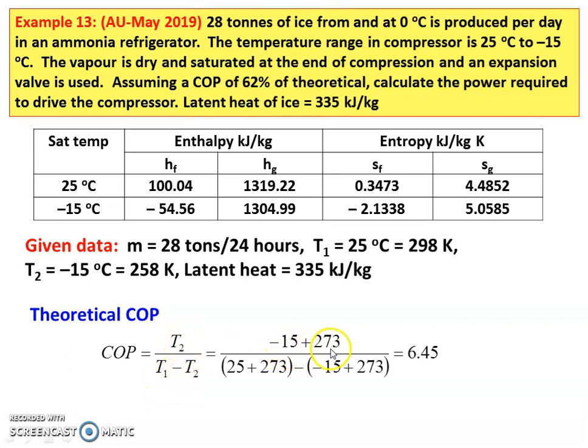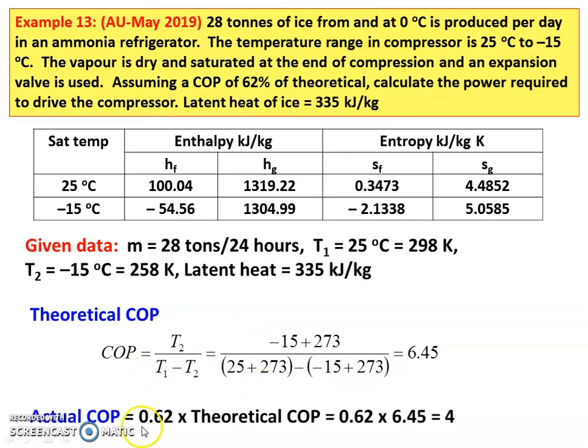So minus 15 plus 273 divided by (25 plus 273) minus (minus 15 plus 273) equals 6.45. The theoretical or Carnot COP equals 6.45. The actual COP is 62% of the theoretical value, so 0.62 into 6.45 equals 4. The actual COP of the refrigerator is 4.